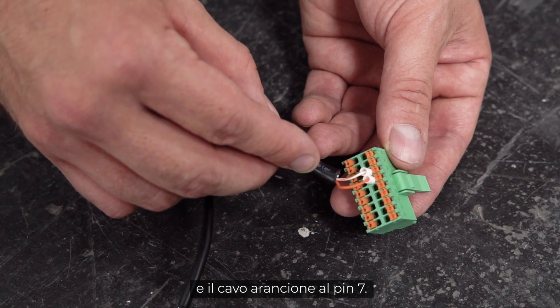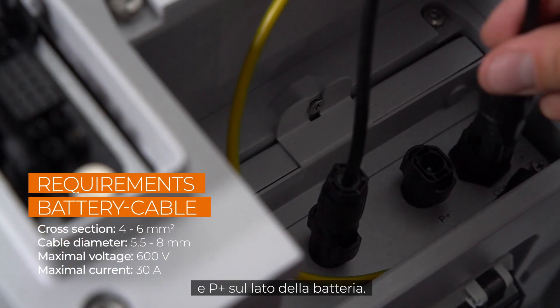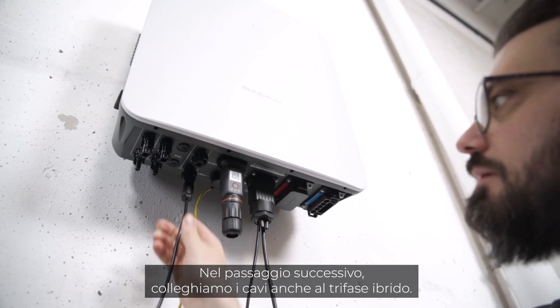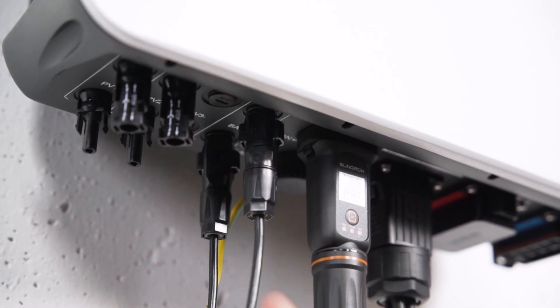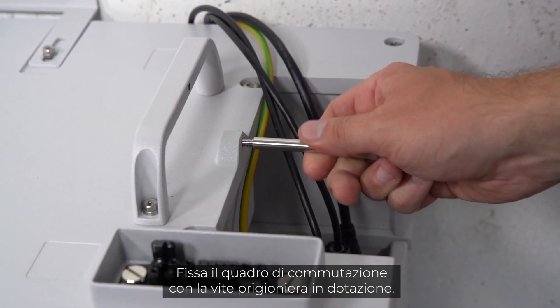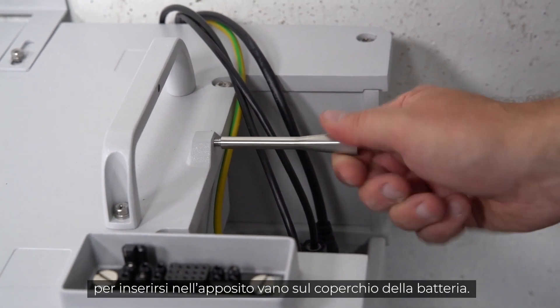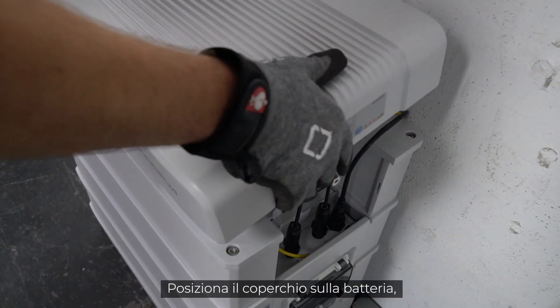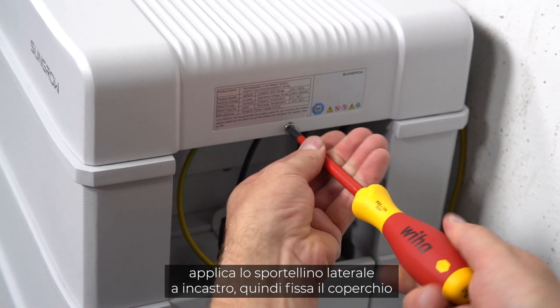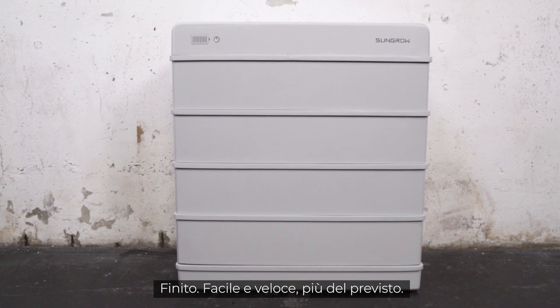Connect the battery power cables to the P minus and P plus port on the battery side. In the next step, the cables also need to be connected to the three-phase hybrid. Fix the cover with the stud, which is part of the delivery scope. Make sure that all cables are correctly positioned to fit into the intended recess in the cover of the battery. Place the cover on the battery and fix it on both sides with the included M5 screw, then clip in the side cover. Quick and easy — beyond the expected.